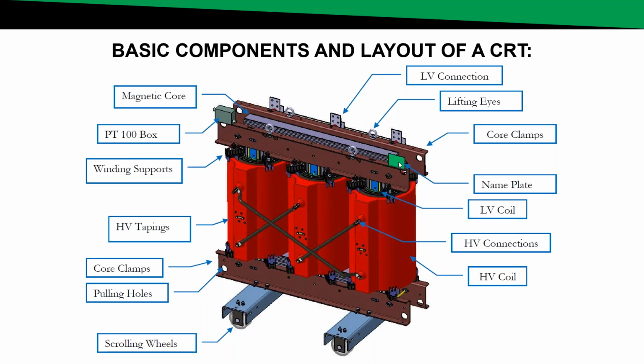You've got your rating plate. You've got a PT100 box, which is basically where the temperature sensors are wired to. We'll get to that a little bit later. You've got your HV tappings, where you can control your voltage. You've got pulling holes, rolling wheels, and then, of course, lifting lugs to move and rig the transformer into position or wherever it's needed.